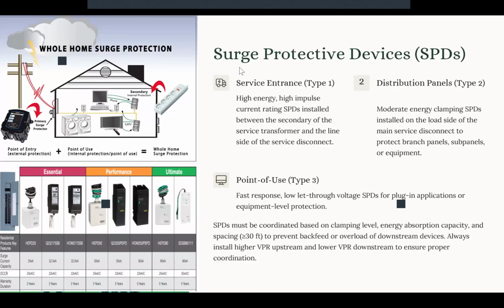Now, at the beginning, we said one of the problems in the power system, which was already addressed in the previous traditional grounding system too, is the surge problem. So we have to have surge protective devices. We have several types of surge protective devices. Type 1 is the service entrance. It normally works with high energy, high impulse current, and it's installed between the secondary of the service transformer, the entrance of our facility, and the line side of the service disconnect.